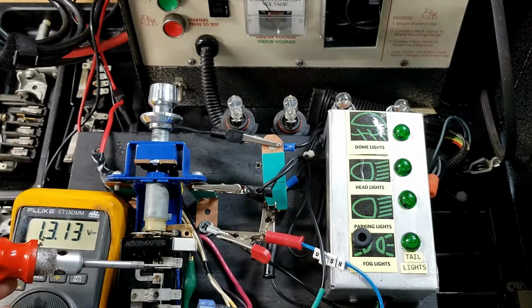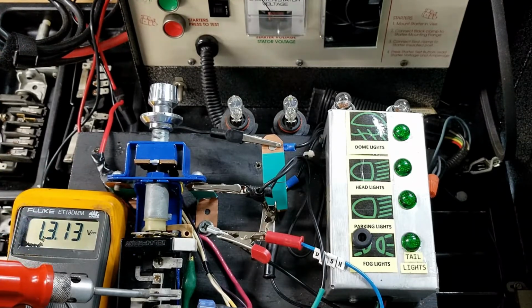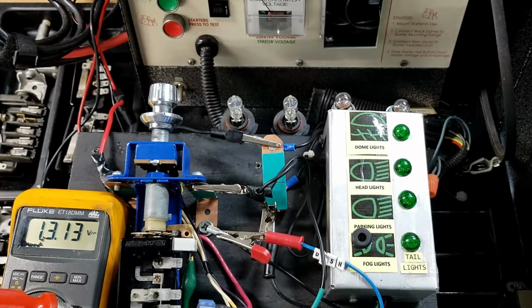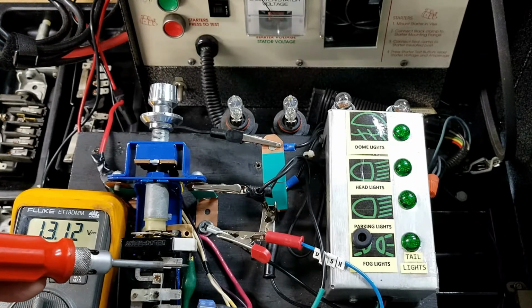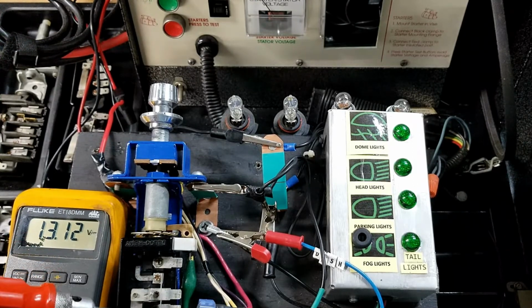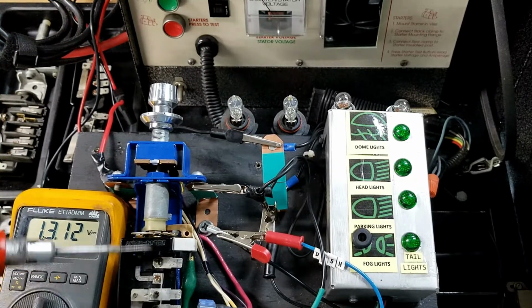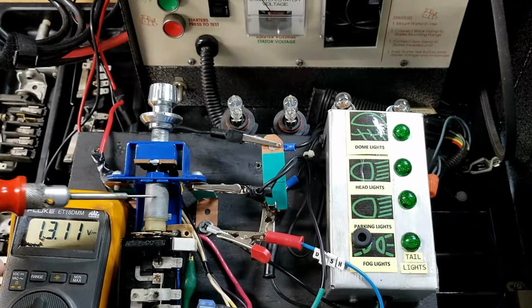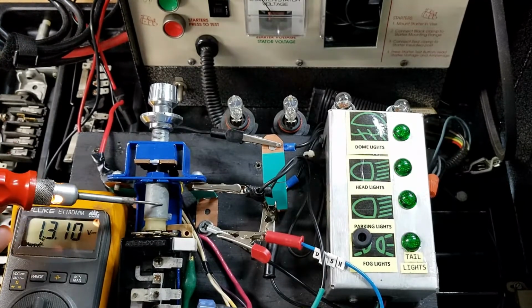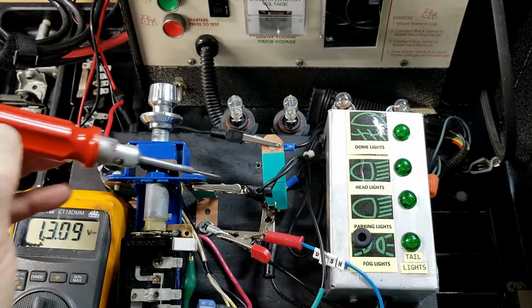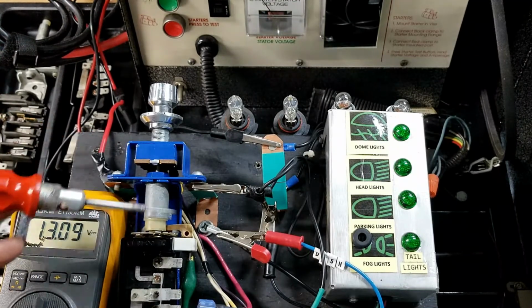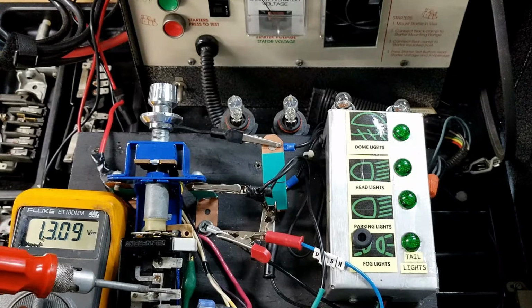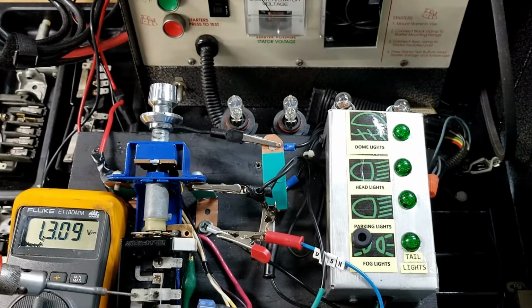Now we're going to probe the terminals and look for any ground connection. We see there's no ground connection. This is an indication that the switch terminals are insulated from ground, and the switch is not connected to ground. So we show that the integrity of the switch terminals are insulated from ground.